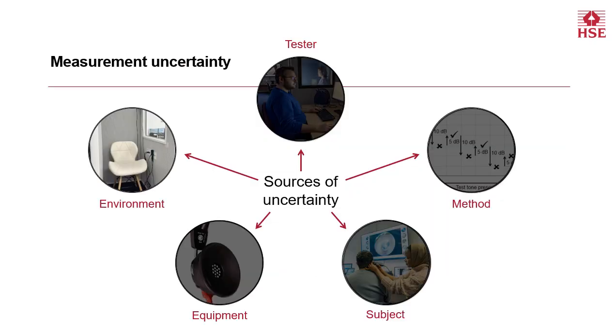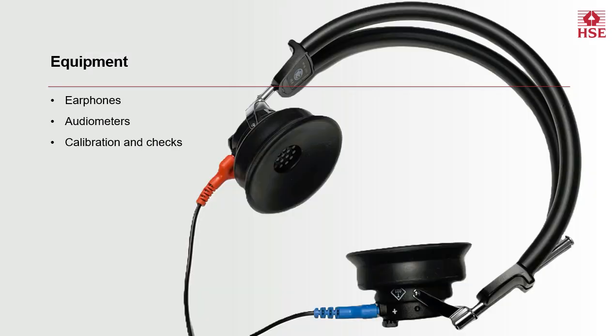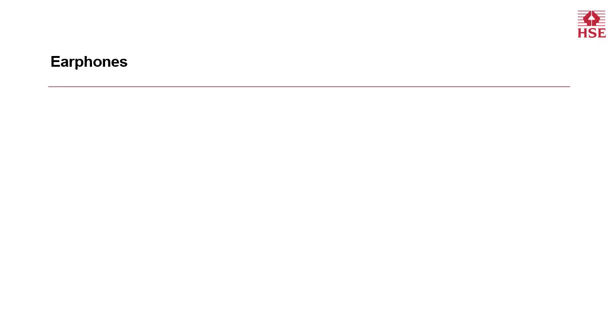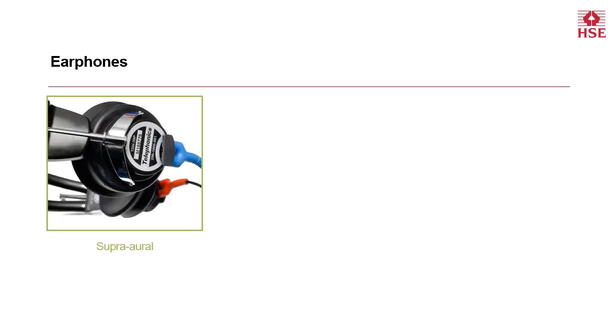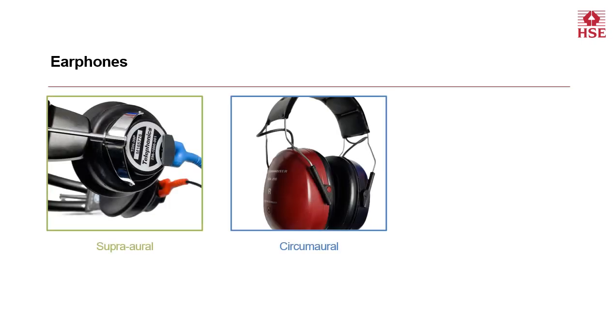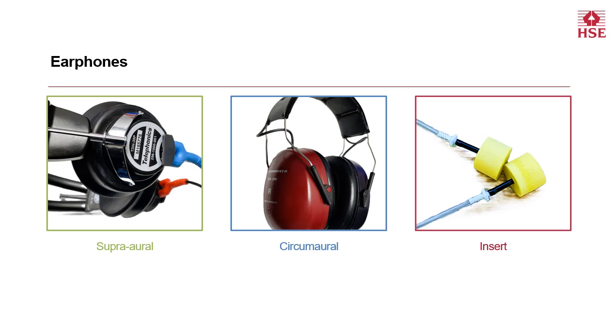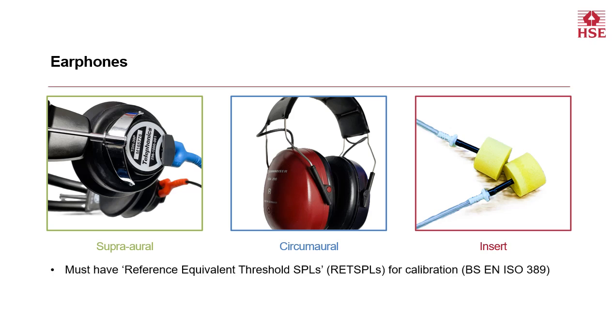Now moving on to equipment. We shall consider the earphones, the audiometer, and calibration in turn. Audiometric earphones come in 3 types: supra-aural, circumaural, and insert earphones. All must have reference equivalent threshold sound pressure levels, or RETSPLs, for calibration. All must have attenuation data.